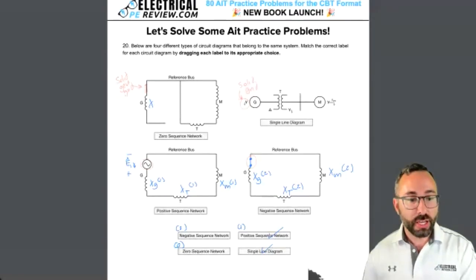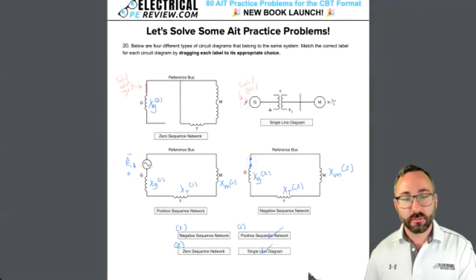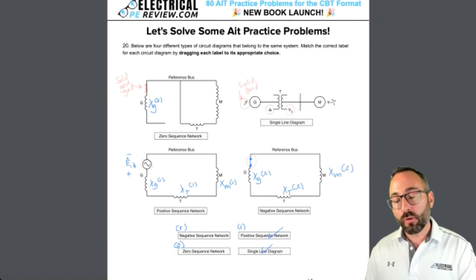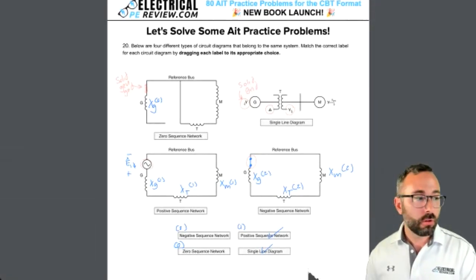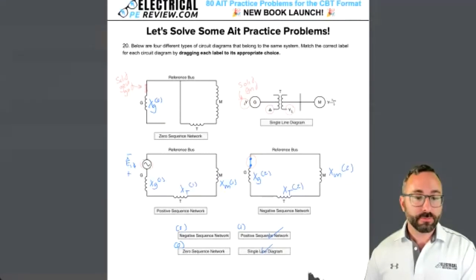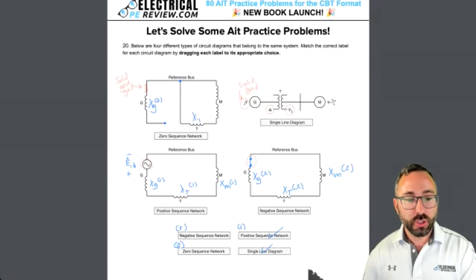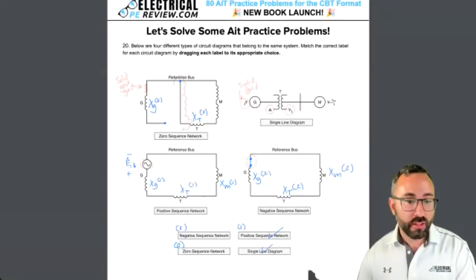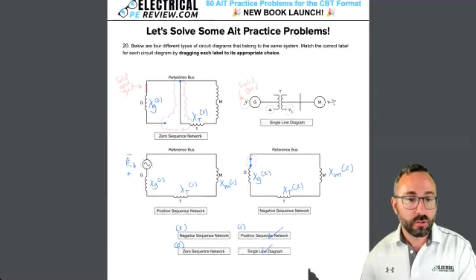Next, I've got the generator's zero sequence reactance. Here's this transformer, a delta Y grounded transformer. It's the most common transformer. On a zero sequence circuit, the delta side is open circuited and the Y grounded side is shorted to the reference bus before connecting to the transformer zero sequence impedance.